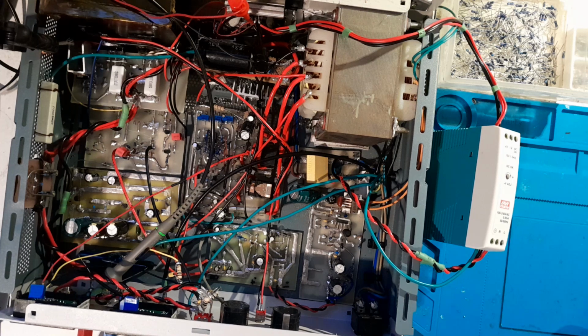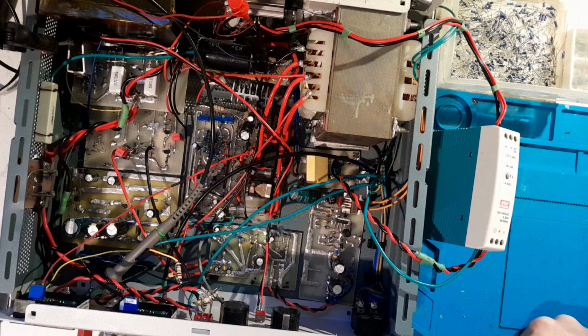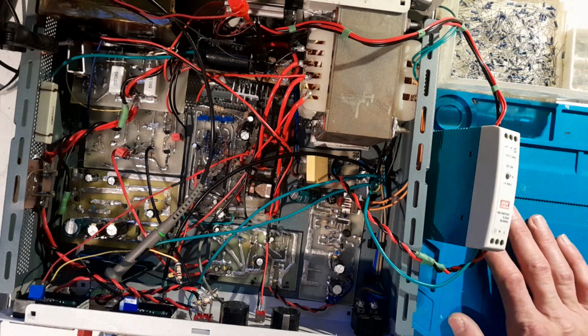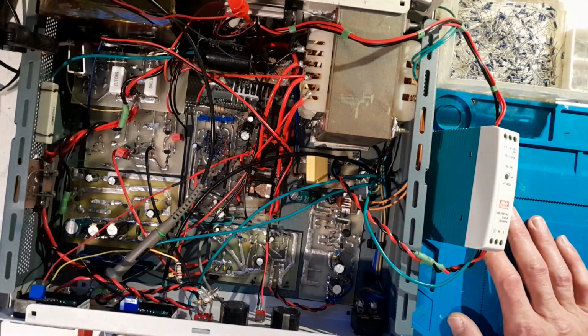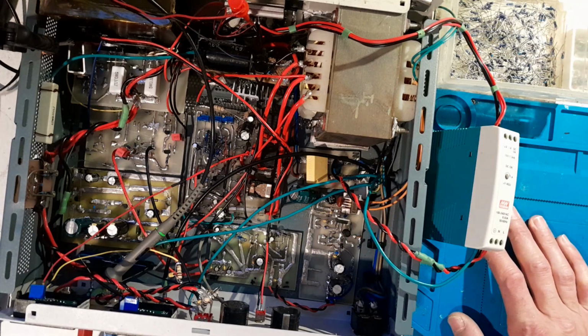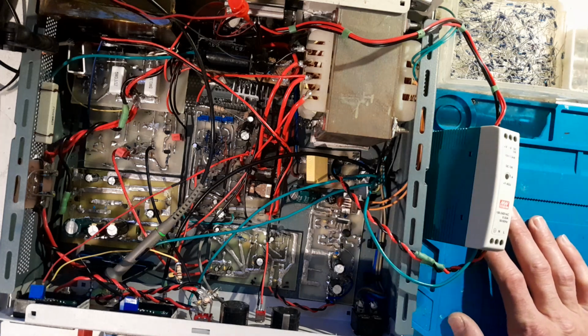I've got a half a volt difference on the tap changing circuit, so it'll turn up to the next tap at 20 volts, but it won't turn back down until 19.5. Even though the voltage doesn't even deflect by a millivolt on the output - just in case there was some sort of load, or it presented some really sharp current pulses - you don't want your relays to start chattering. There's also a few other interesting techniques in there to make sure things can't go sour like that, like two relays coming on at the same time, for example.